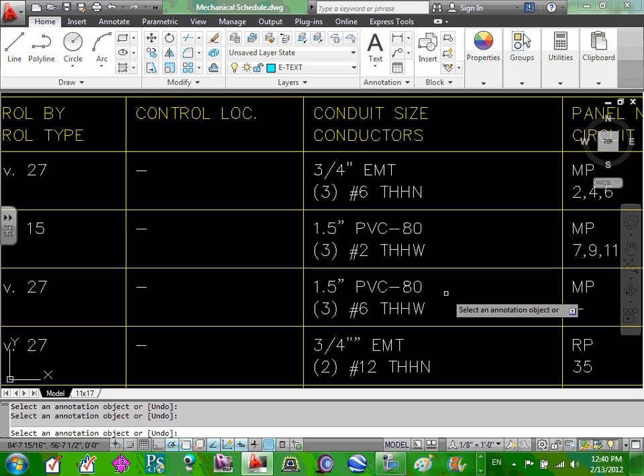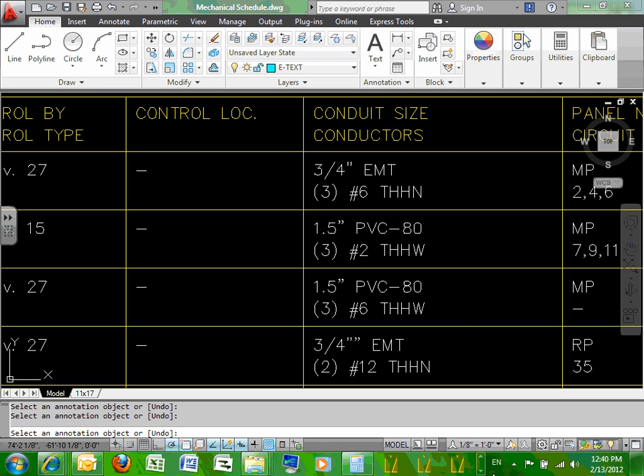The full load amp, remember the full load amp for this? Let's go size it right away. Full load amp for this one, guys, I'm going to size based on 91 amps. Why 91 amps? Because it's the chiller, from right here, 91 amps. So let's go size for 91 amps and see what we come up with.